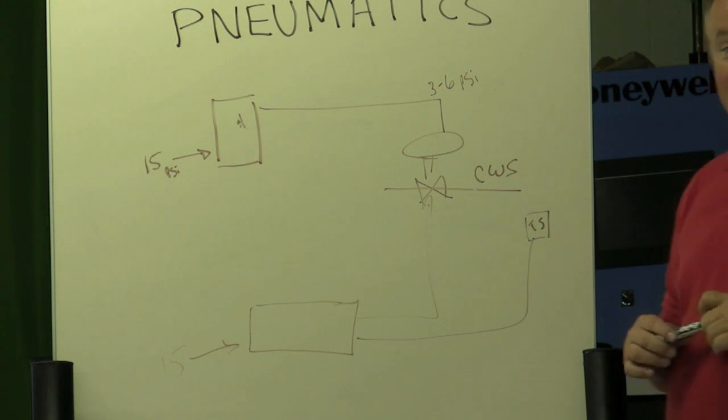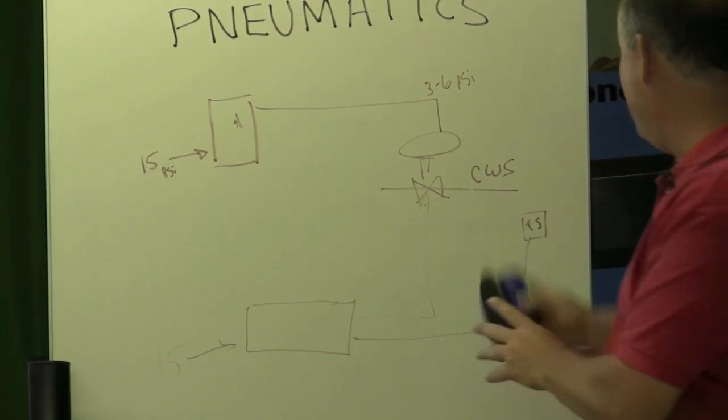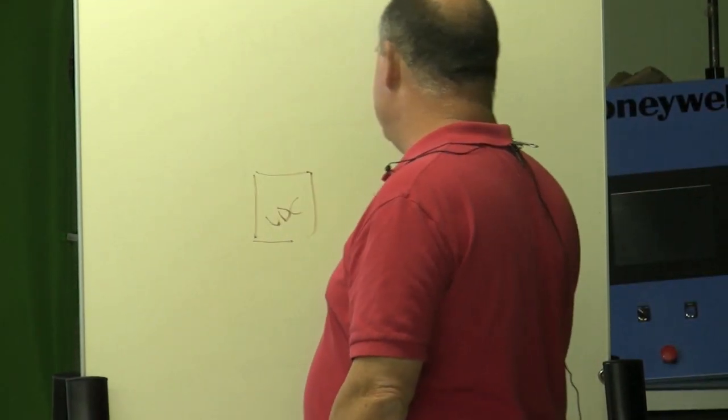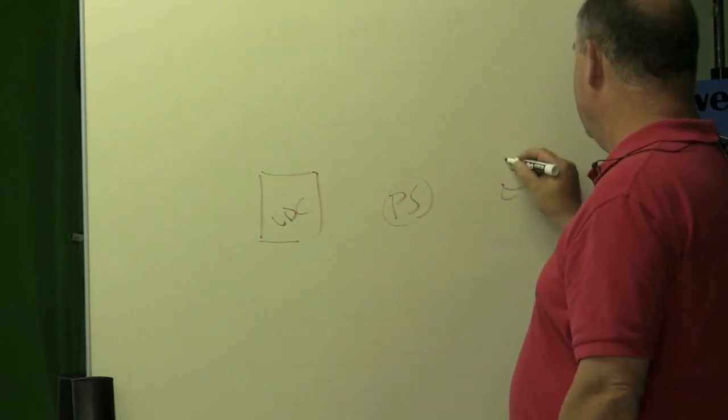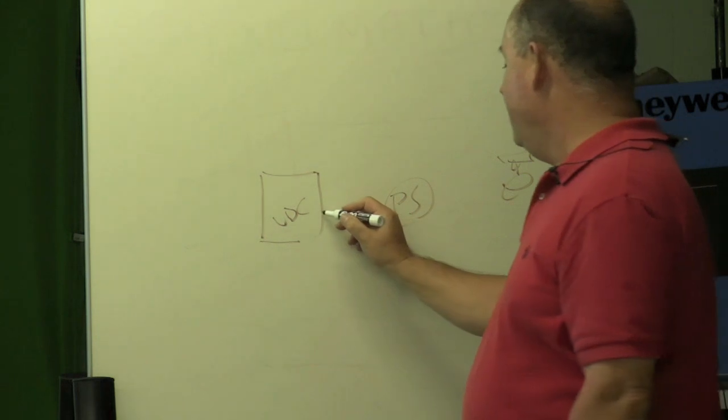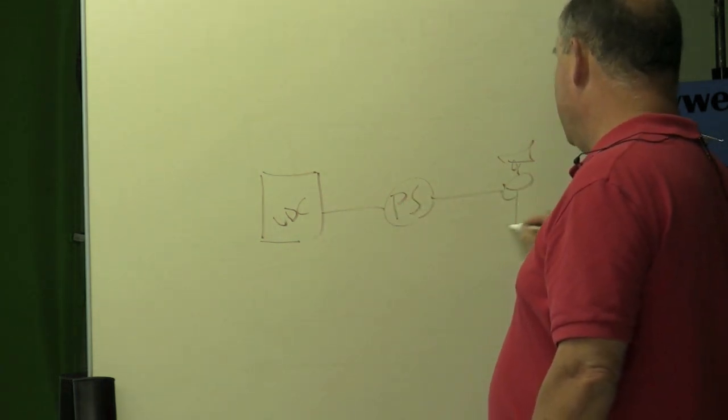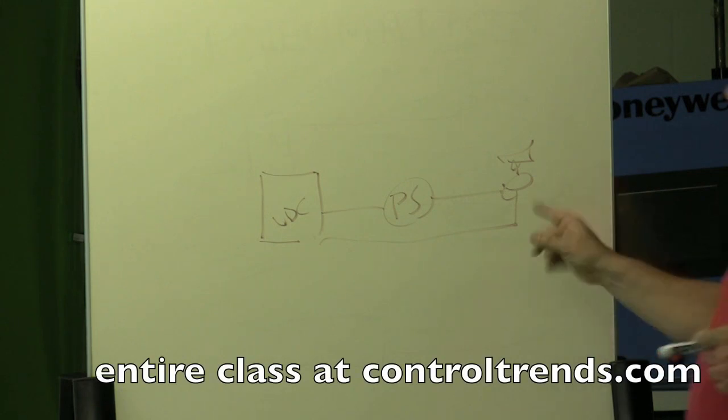They have to be powered. They'll give you 4 to 20, but only if you power them. A couple ways to do that. You asked about the UDC giving its own power. Many times you'll do a UDC, a power supply, and then your little transmitter, and you just wire these guys in a loop. It's always going to be a loop, and it's got to be powered. So that's one way to do it.